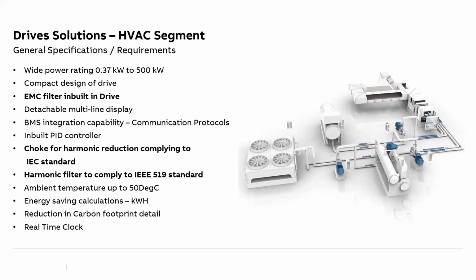For example, we can have a return air temperature feedback. Temperature sensor feedback from the return air duct can be given to the VFD. If we have set a certain temperature, then it will continuously monitor that. And if that temperature has been achieved, then it can control the external device, which in this case is a chilled water valve. So if the temperature is achieved, it will modulate the chilled water valve and reduce the consumption of chilled water. So your chilled water flow also reduces.